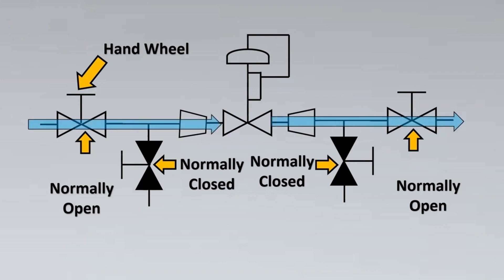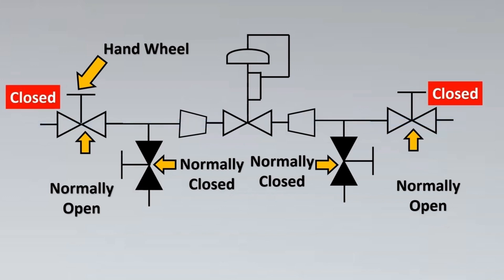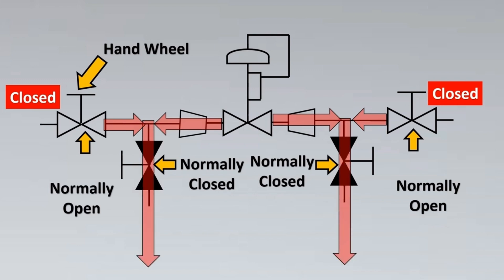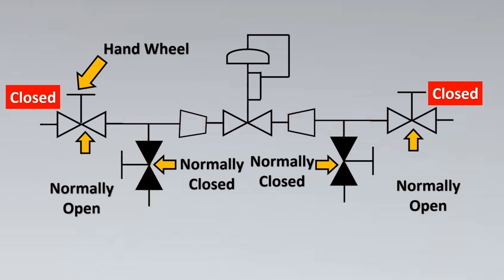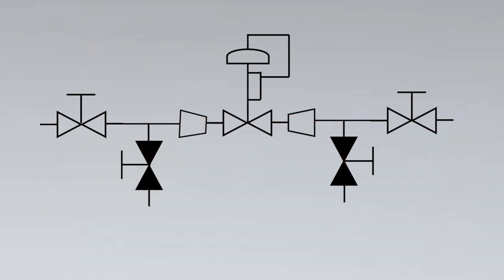In normal operation, the control valve allows flow to pass through it, as shown by the flow line. When we need to remove the control valve for maintenance or issues, we close the two isolation valves on either side. There is fluid trapped in between, so to fully isolate the control valve, we open the normally closed drain valves to drain the liquid out. Then we can safely remove the control valve from service. This NO/NC configuration is commonly used for isolation purposes.